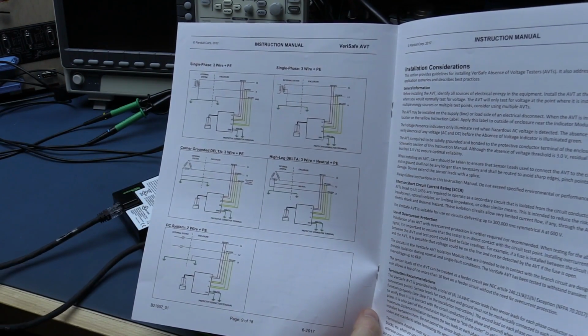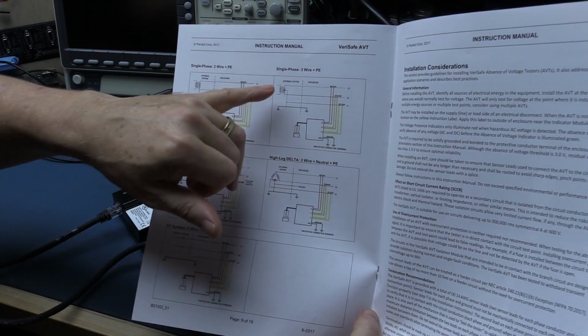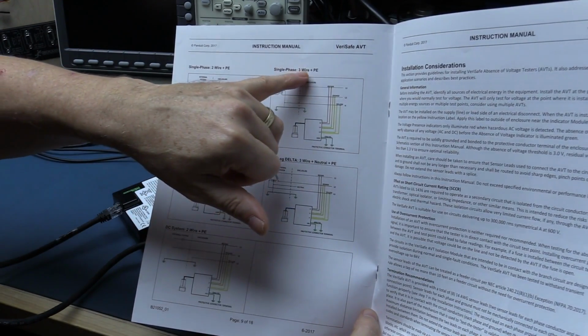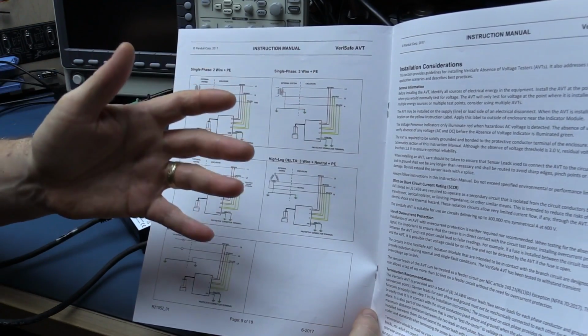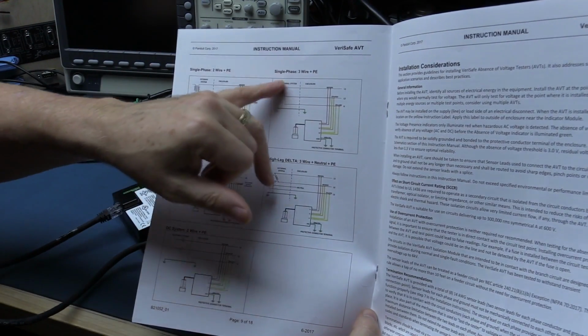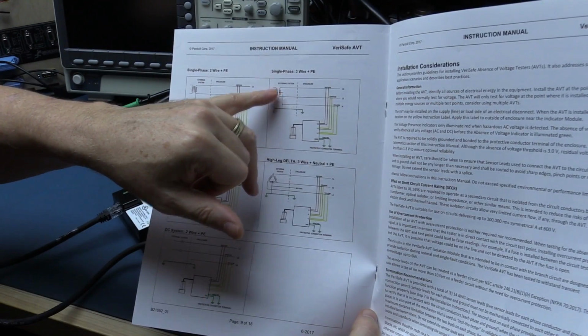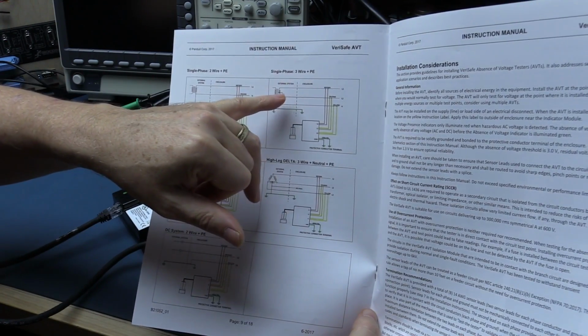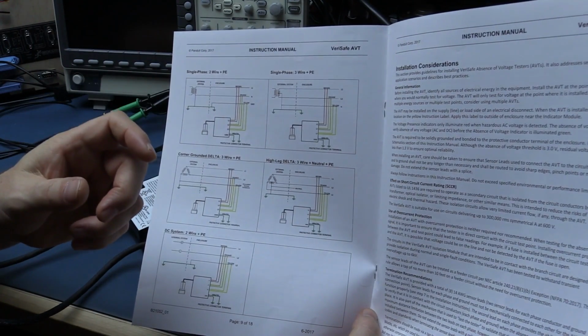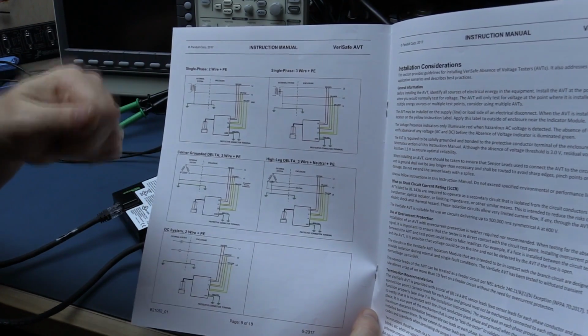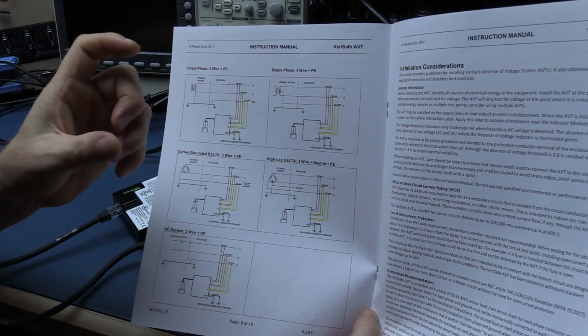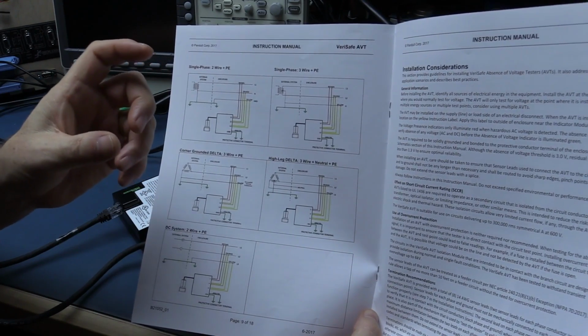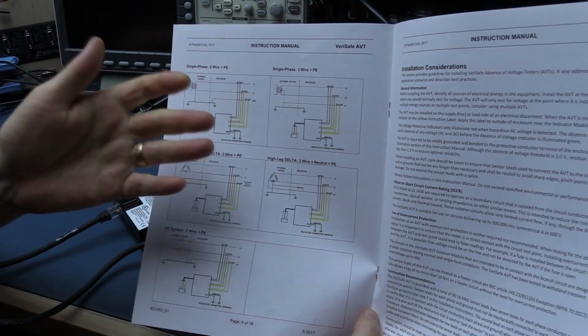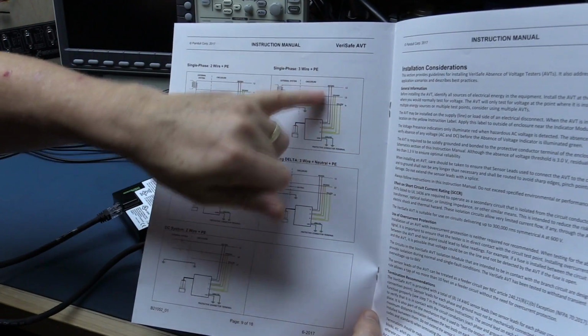What we also have in North America, and most households actually have this provided to the house, is they're calling it here single phase 3-wire, but it's kind of like a 2-wire. It's 2 phases. They have a transformer out in the street, and then you've got a center tap going to ground, and each side of it being fed into the house. So when you have your junction box, every other contactor, every other fuse breaker is connected to a separate phase. So if you go across the phases, you can actually get 220 volts, and if you go to a single phase and neutral, you get the 110. So this is able to handle that as well.